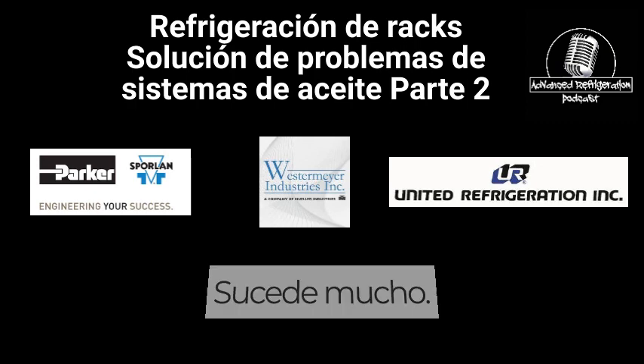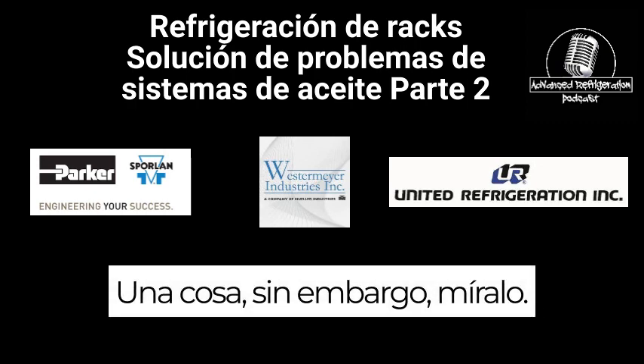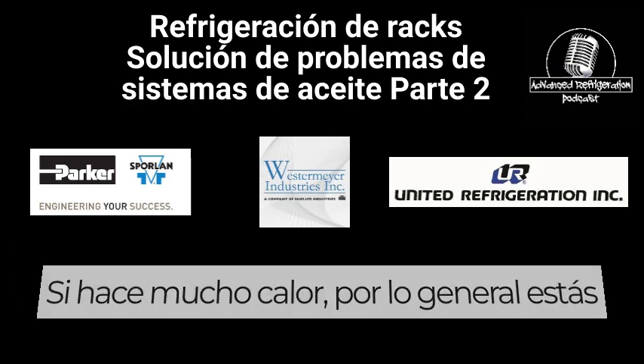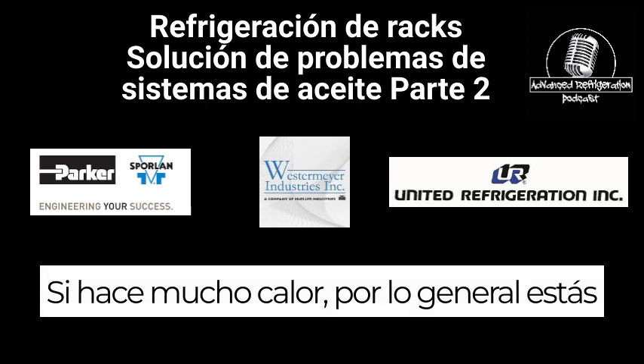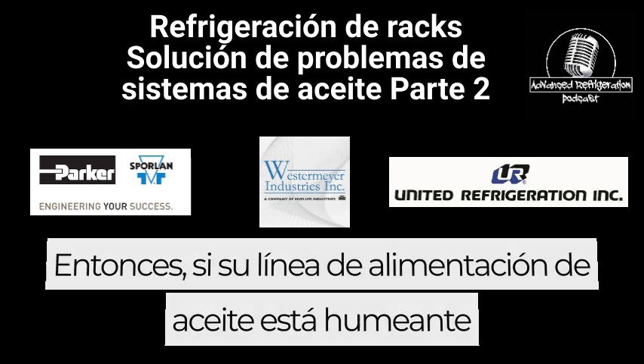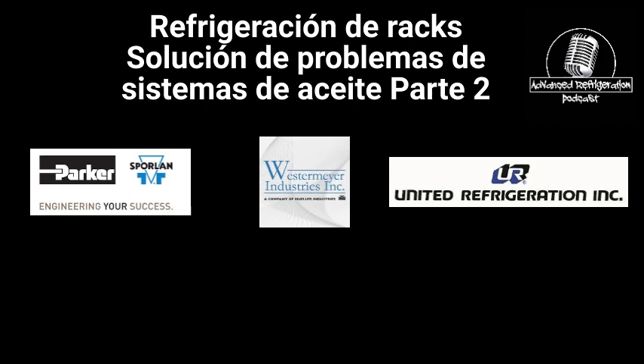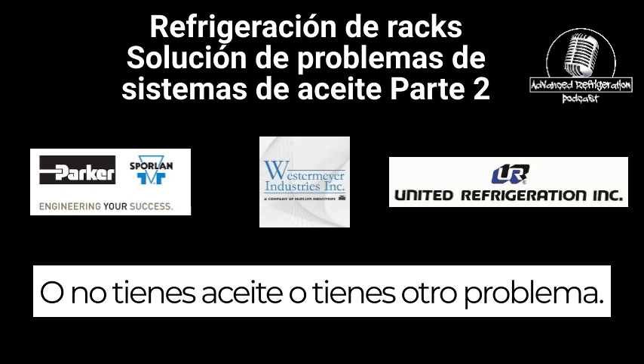Yes, correct. I mean, it happens a lot. One thing to look at, just check the oil feed line. If it's smoking hot, generally you're getting some vapor through there. So if your oil feed line is just smoking hot, going into that oil float, you're getting vapor in there. You're either out of oil or you have another issue.